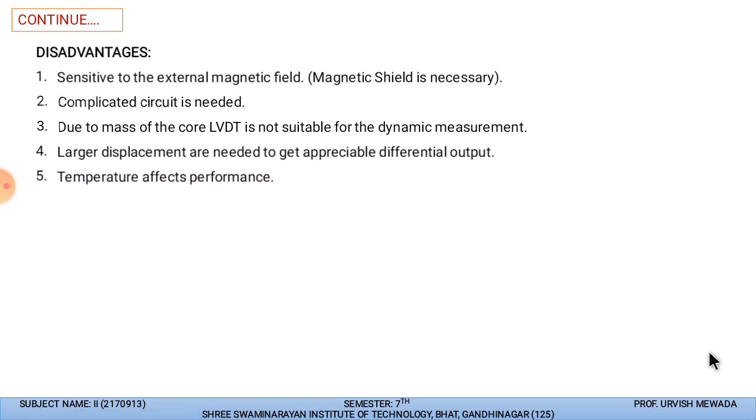Then temperature affects the performance. The surrounding temperature will not affect it much, but if the internal temperature increases, the winding resistance will change, and so the output of the LVDT will change. Then the dynamic response is limited. Then it is affected by vibrations. When vibrations are generated, the chances of harmonics occurring are more, and that can affect the performance of the LVDT.